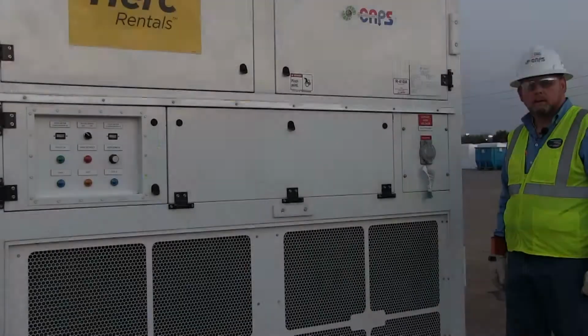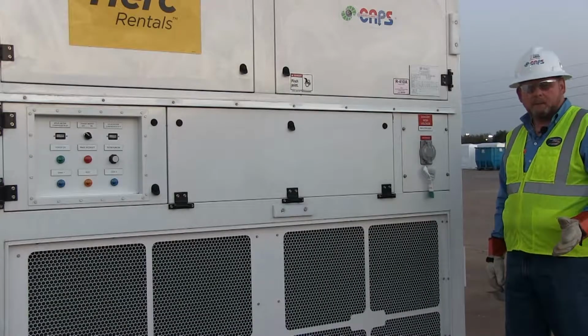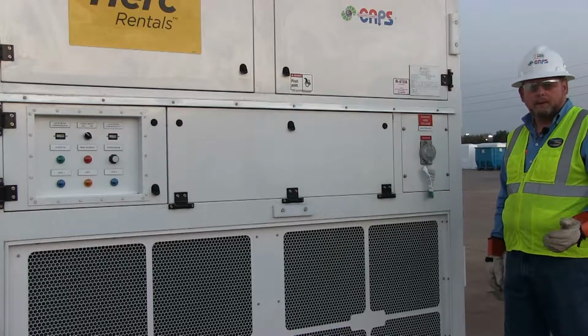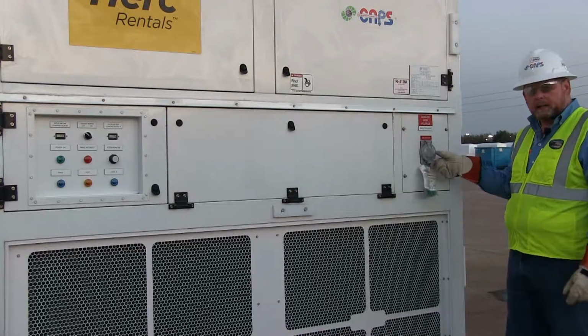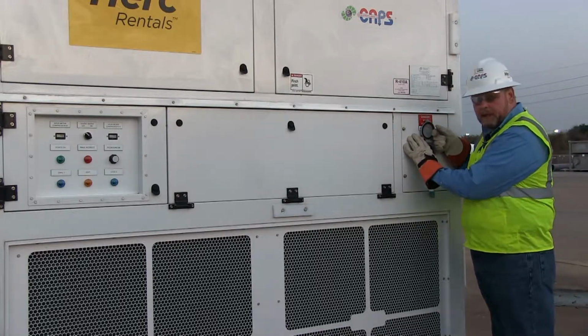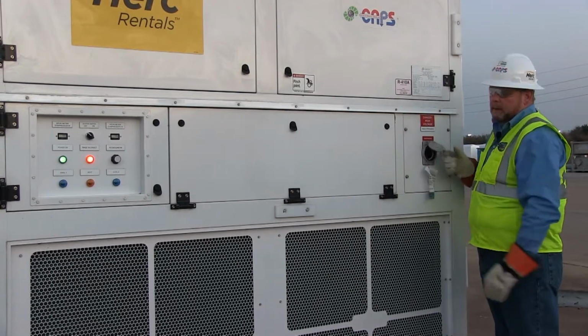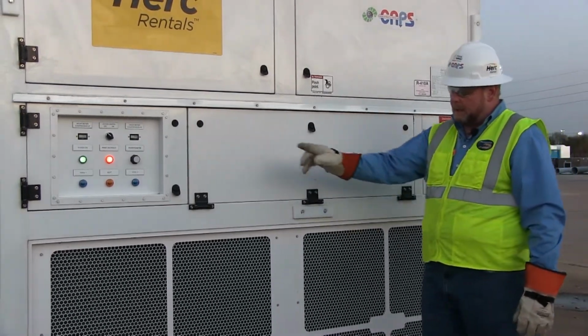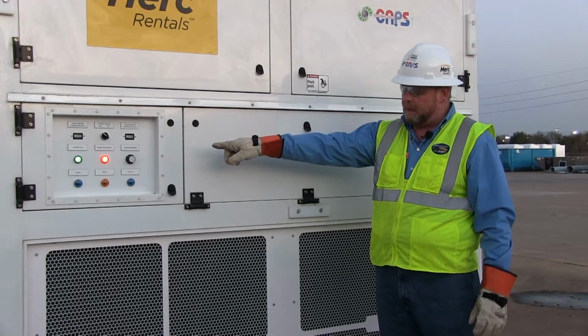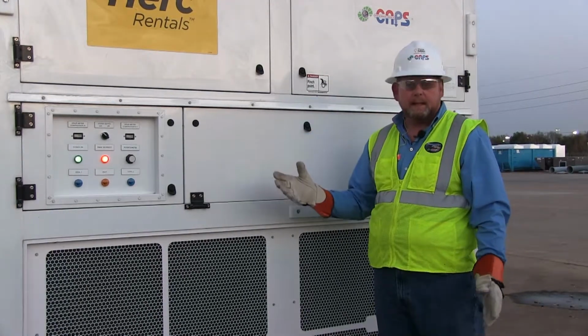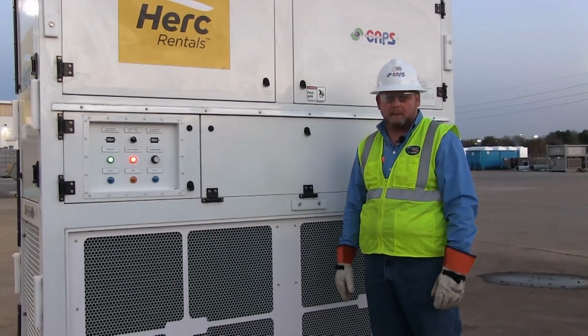We've energized our main 460 volt power. The next step now is to turn on the integrated breaker, which will energize the machine. At that time you can see the power light came on, but we also have a phase incorrect light on. That indicates that two of our phases are backwards.